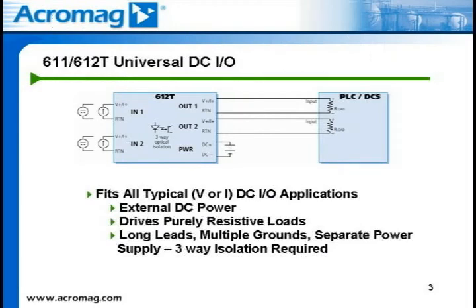The 611T and 612T isolated transmitters fit all typical types of DC I/O applications. Three-way isolation is the safest choice when retrofitting or expanding an existing system when uncertainties about isolation of instruments in each current loop exist, or the grounding scheme is unknown. In applications where the power supply needs to be isolated, the 611T and 612T can be used because they are powered by an external power supply with separate power terminals, and they source current to purely resistive loads. This means that a power supply is not required in the output loop to drive the output signal.